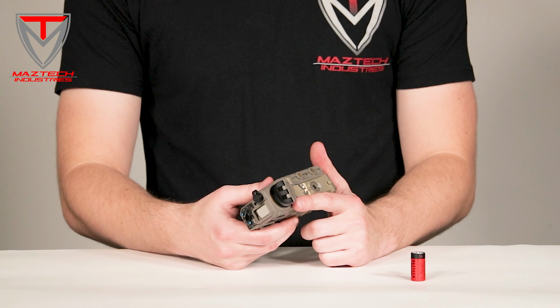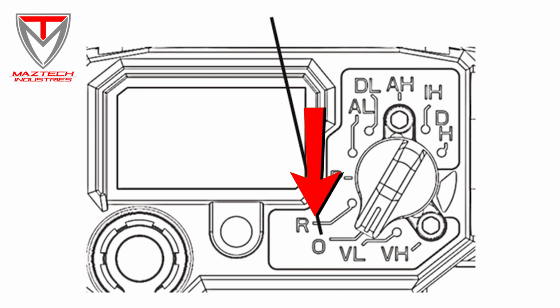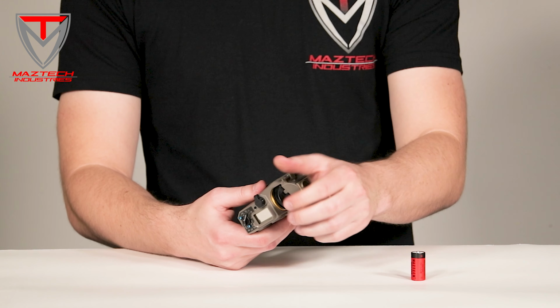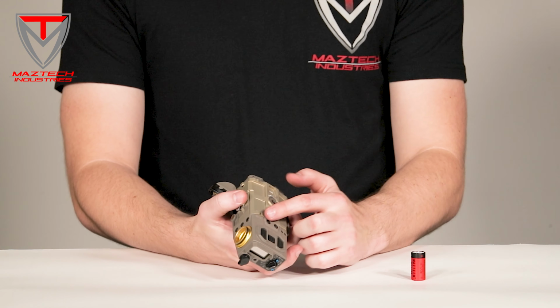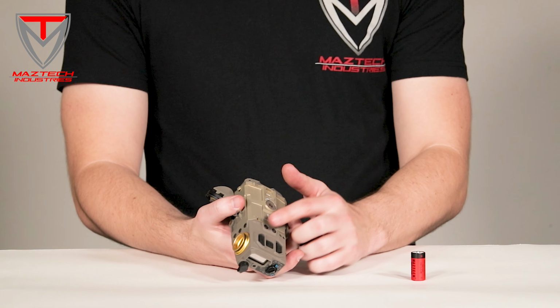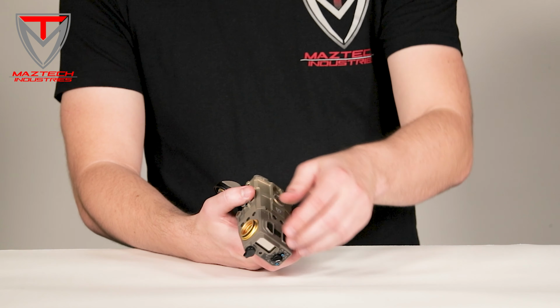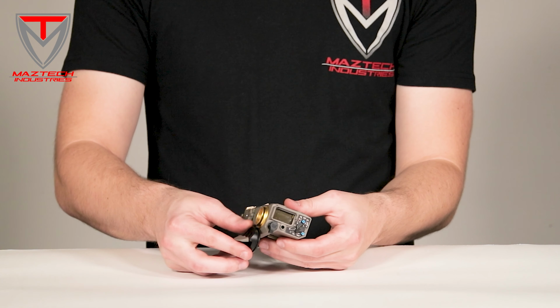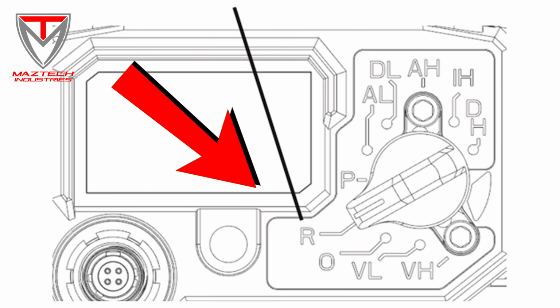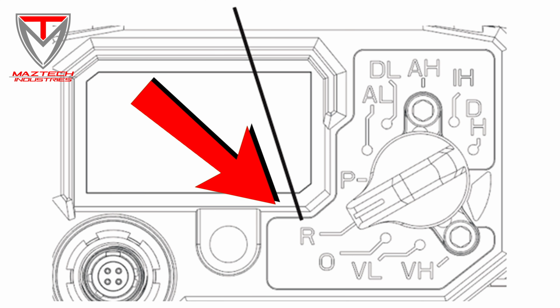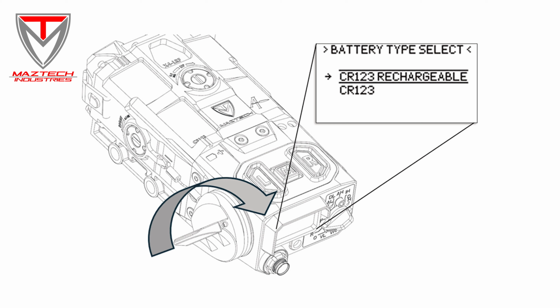To install the battery, turn the mode knob to off, unscrew the cap, insert the battery following polarity indicators, then hand tighten the cap. Turn the knob to range and confirm the battery type shown on the display. Use the L and R buttons to adjust and press M to confirm.